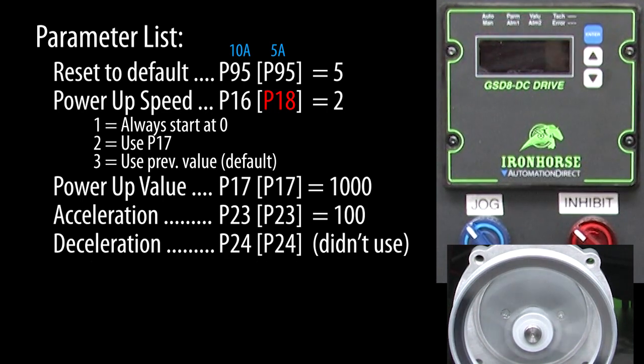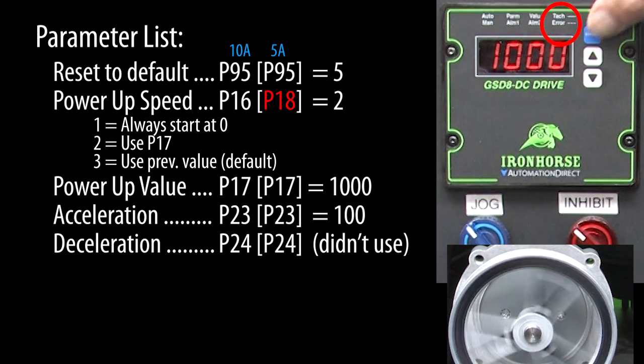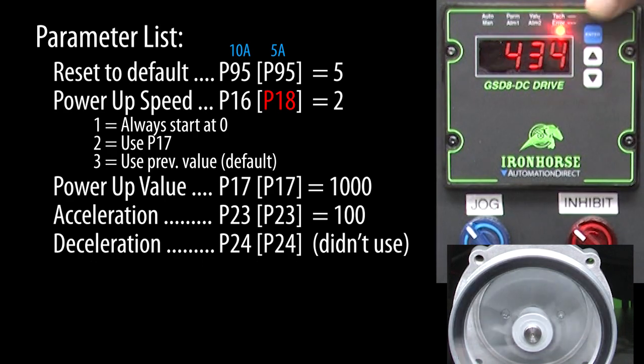I'll power down, give it a second, and power back up. Briefly pressing the enter button shows you the current tach value while the tach LED is lit. I'll press it a couple more times and sure enough we see it took about 10 seconds to ramp up to speed.